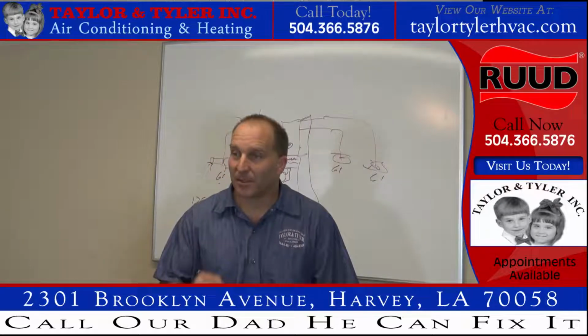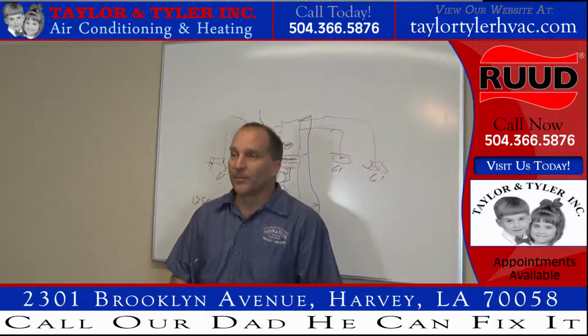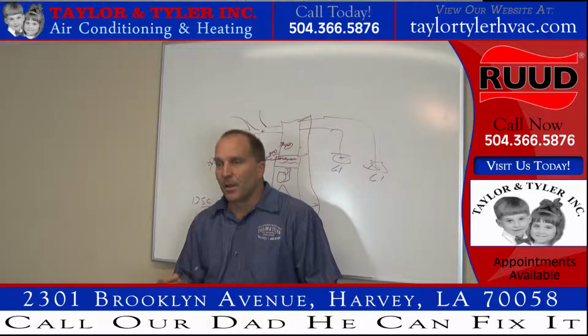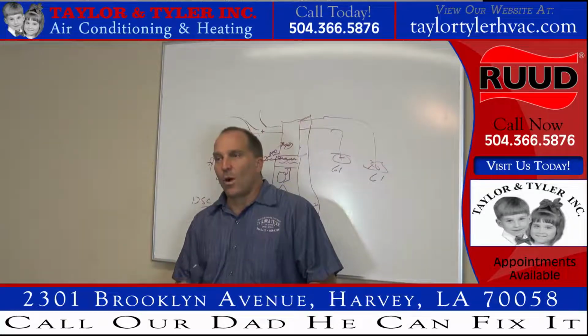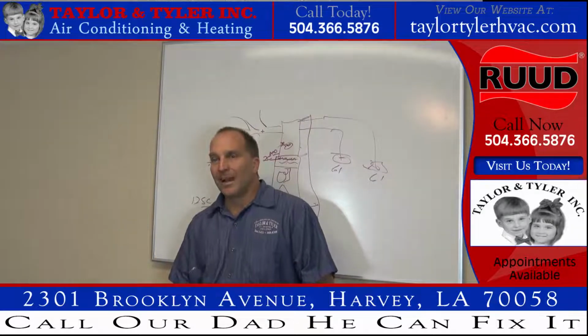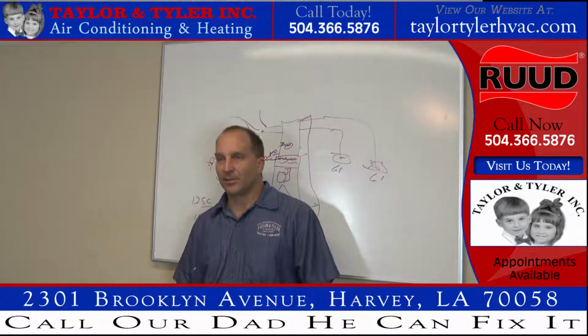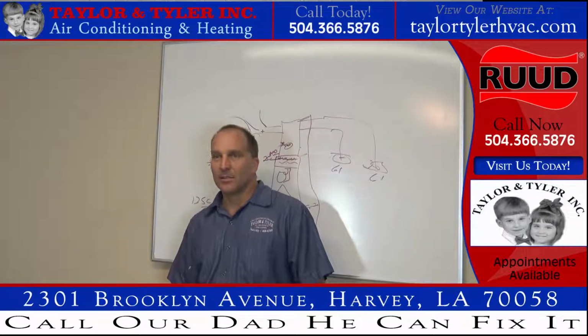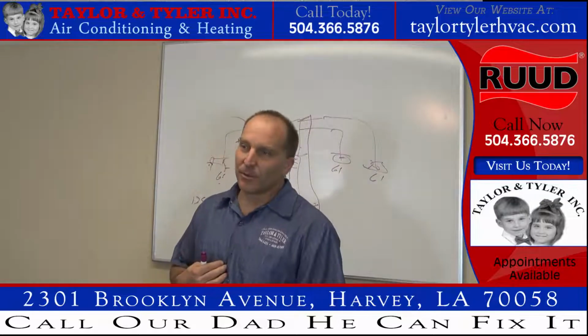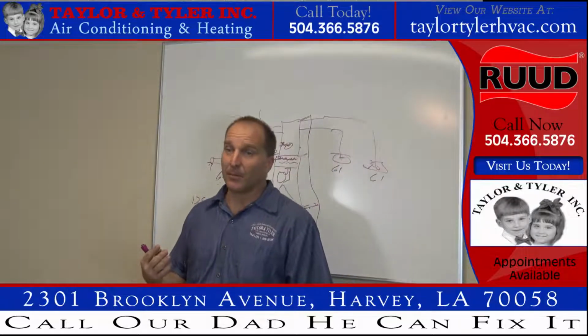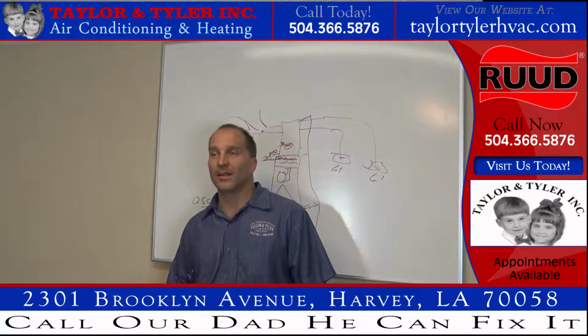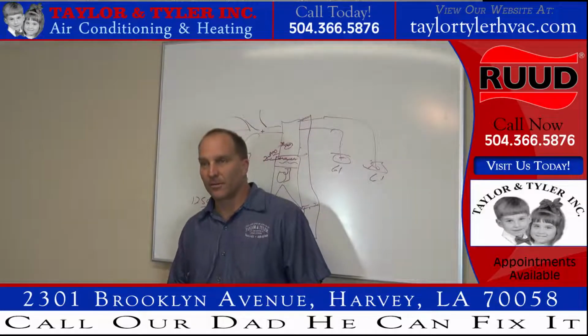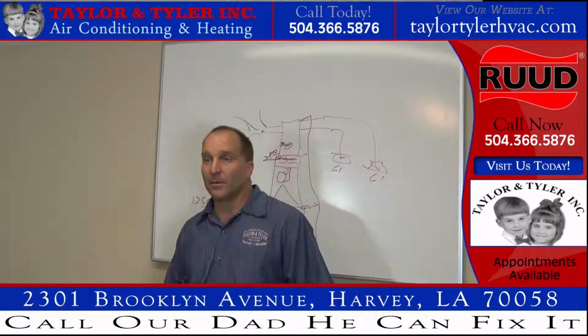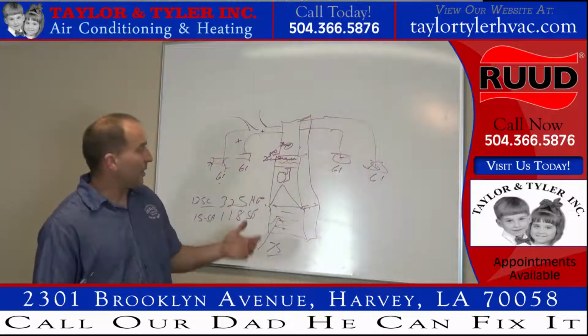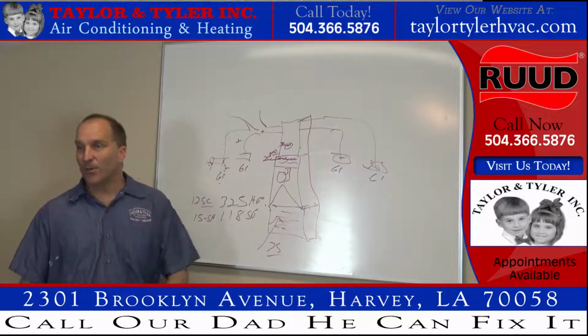So here's what happens. You call me and go, Eric, I can't figure out why my system doesn't cool. And you don't give me all the information. If you don't give me all the information because you don't go look at everything, I'm going to diagnose it wrong because I don't have all the information. Did you check your delta T? And you go, well, in this case, my superheat, my subcool, and everything's perfect.